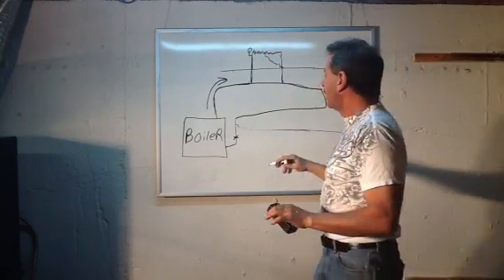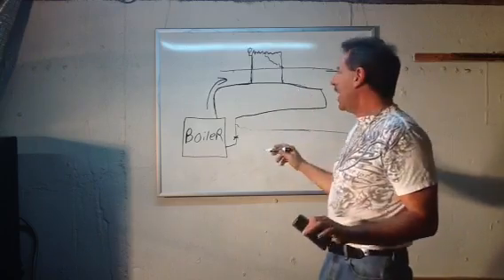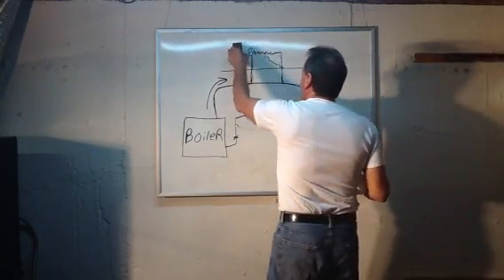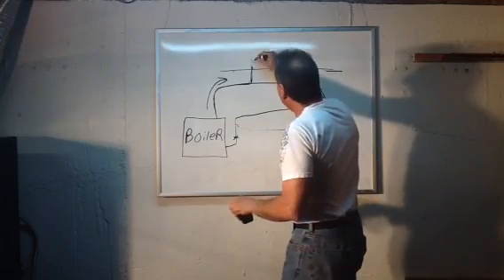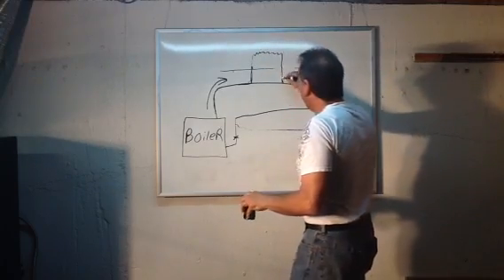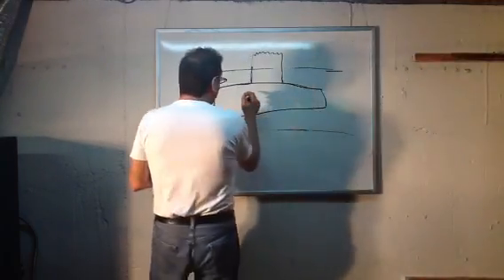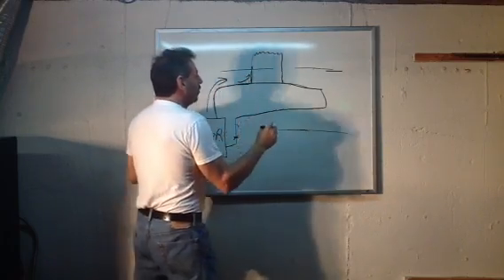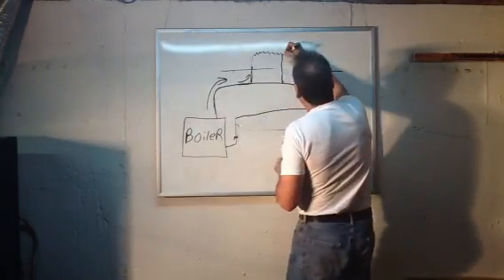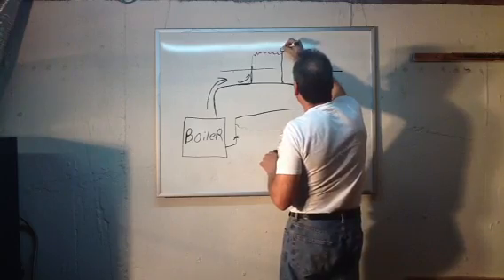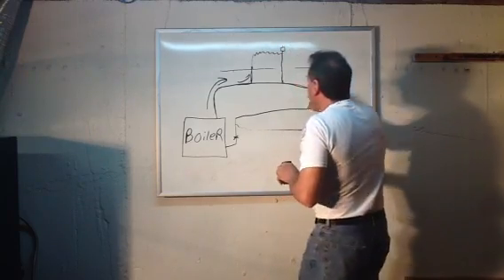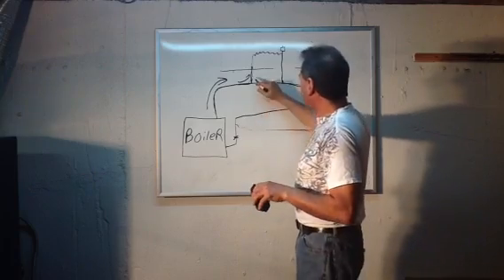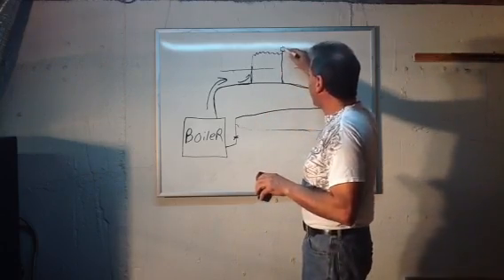Anytime you have a radiator on a floor, if the entrance way to the radiator is on the left, the water flow, the bleeder must be on the opposite side. It can't be on the same side as the entry, it has to be on the return side of the radiator.